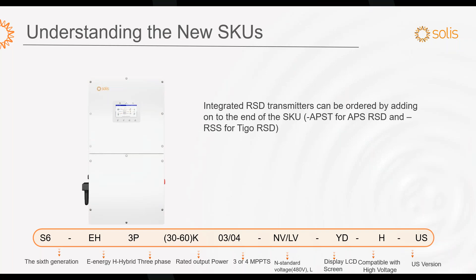It has usable PV power up to 200% of inverter rated power. That 200% oversizing helps improve utilization of PV generation as well as make it flexible in deployment. It also supports 40 amps of PV input current, eliminating clipping and supporting the super high powered bifacial modules in the marketplace.